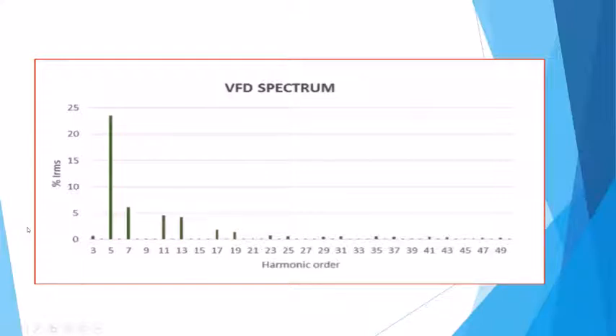So what they're talking about is, especially in a VFD application, you get these harmonic spectrums out there, and you get third, fifth, and seventh, and that means 3 times the 60 hertz. So it's like 180 hertz values here, 5 times and 7 times. And these are on a 3-phase circuit, which you typically see. You also get a lot of these clear out in the 47, 48.